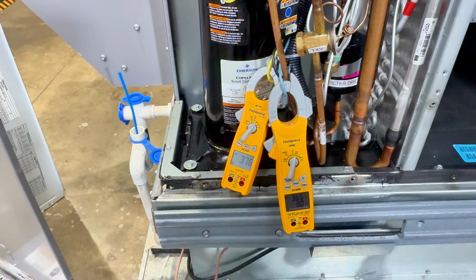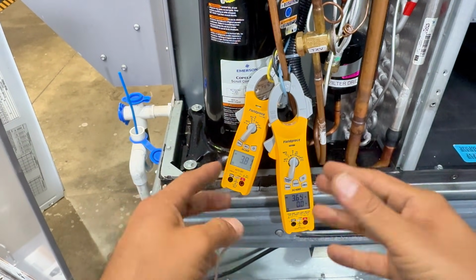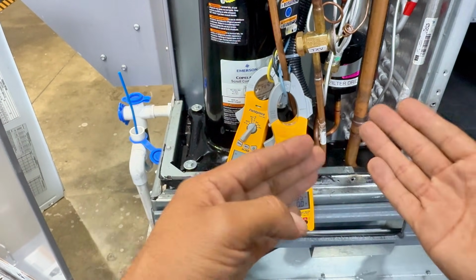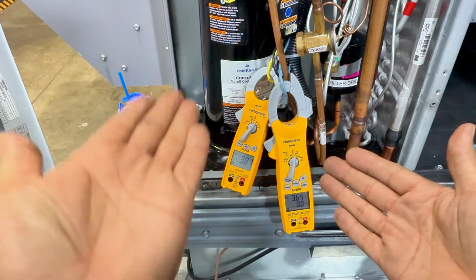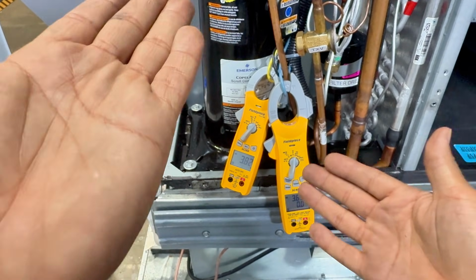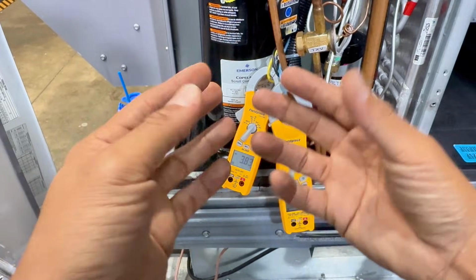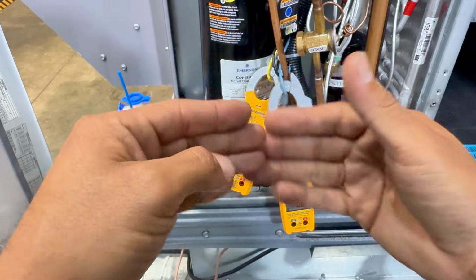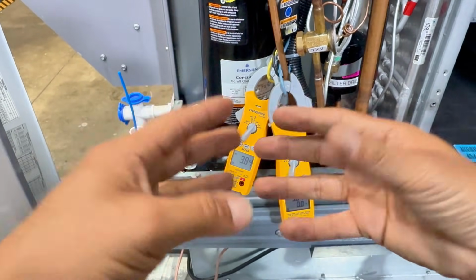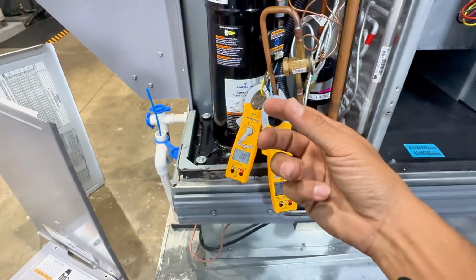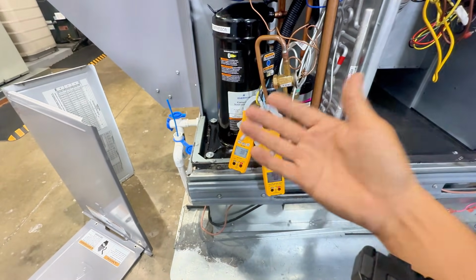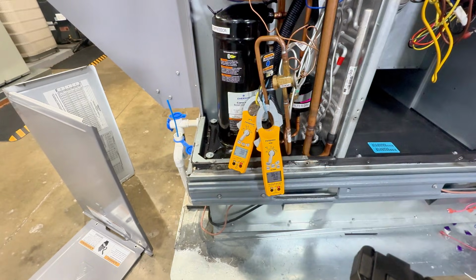when the capacitor is healthy? Sure, when the cap is kind of bad, you'll see that. But when the capacitor is good and it pulls that much saturated current, inrush current, even though it drops down to 4, something could possibly be going on internally with the windings of the compressor. So that's another little thing you could check, by checking saturated and inrush current on your run winding.